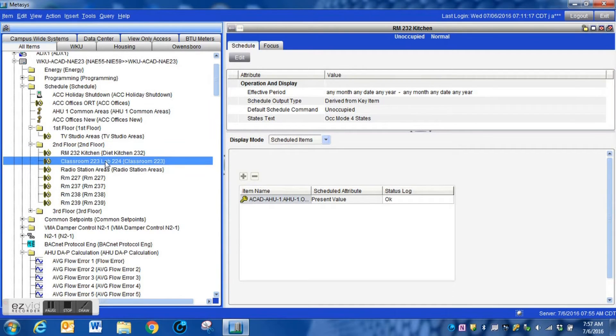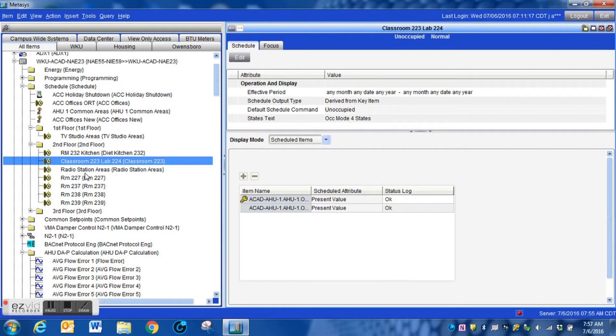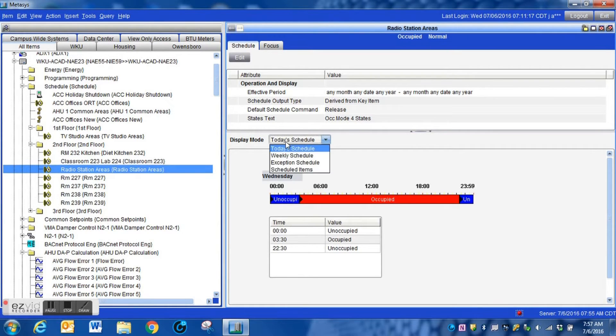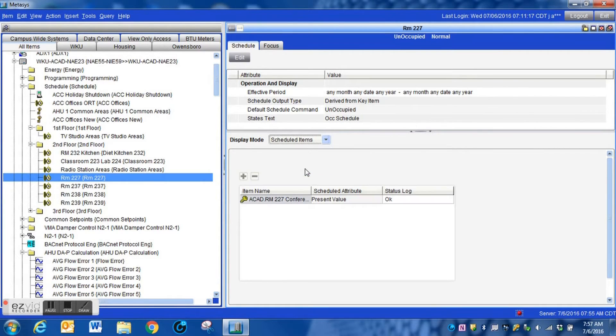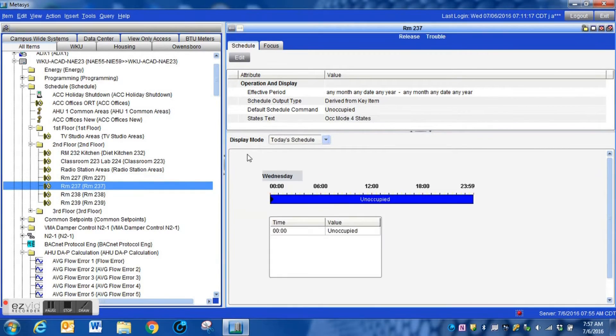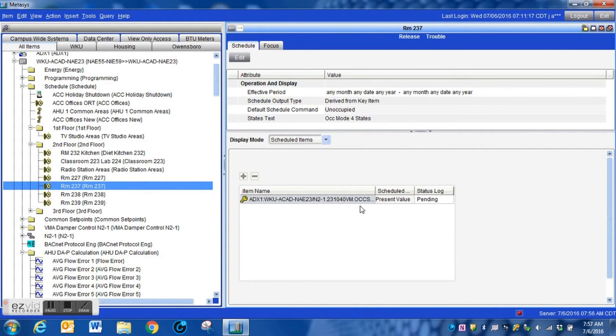You can see here I'm going through every one of these schedules, just verifying that they are still all active. We will run into some where points no longer exist within the system. You can see this one here says "pending" — this is the original schedule for one of the controllers that was removed, so that is going to be an unbound reference. It's something we can get completely rid of since it is no longer used.